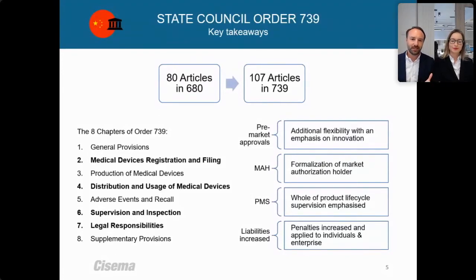So what are the key takeaways for medical device and IVD manufacturers importing to China? There's a couple of messages: increased flexibility in the pre-market approval process, formalization of market authorization holder regime, an increased focus on whole of life cycle supervision, and increased liabilities where laws are breached. Of course, what this means in practice is still to be clarified.